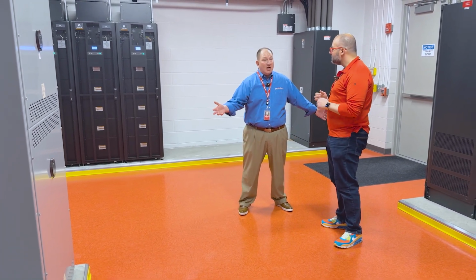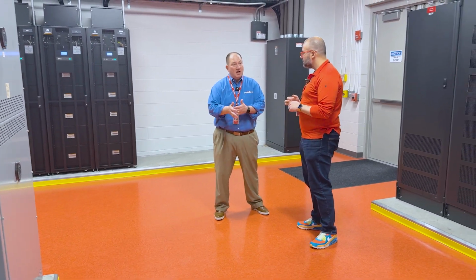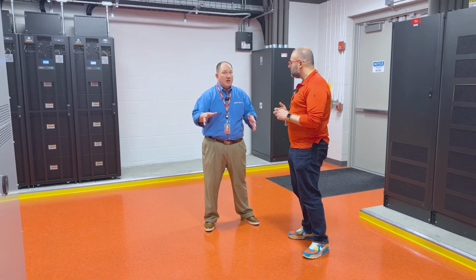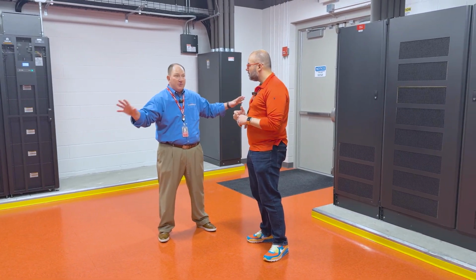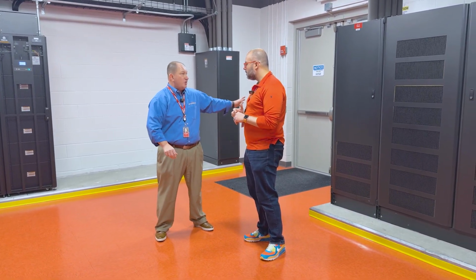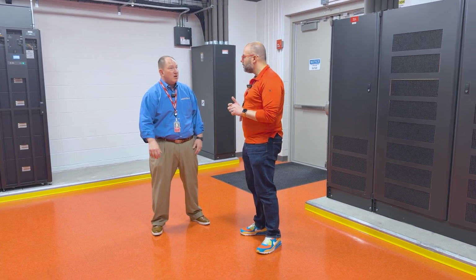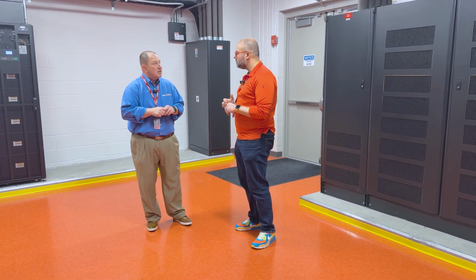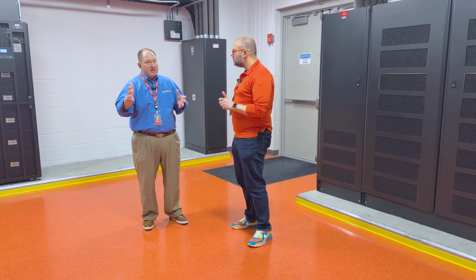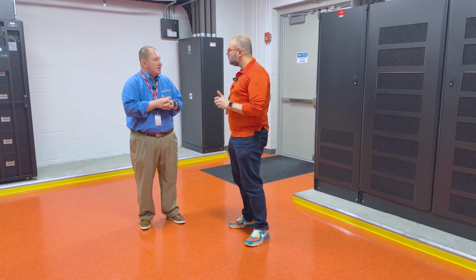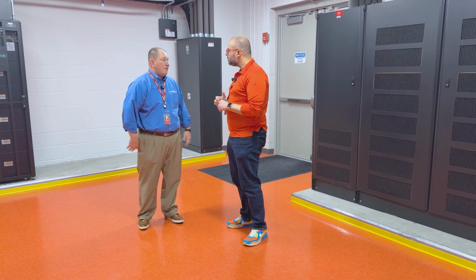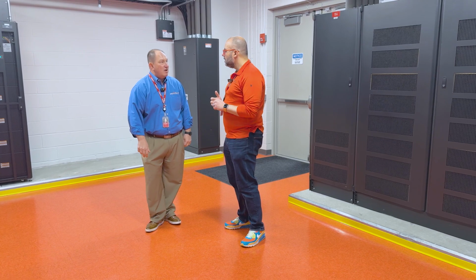That's correct. Like I talked about, some of our stuff we do on a quarterly and annual basis. Quarterly, we actually come in and send all this load, the data center load, to the generators to ensure all the systems work. We have a sequence of operations we follow, and we basically simulate a commercial power outage, sending all the load in a controlled environment. That's a test we do every quarter.